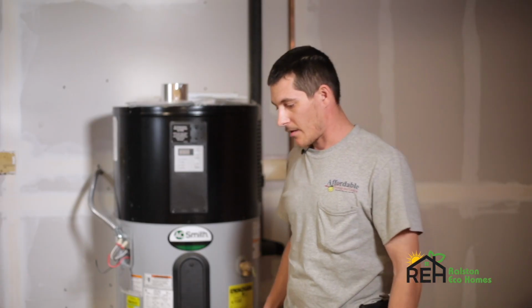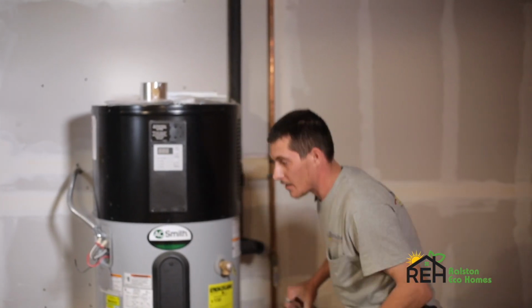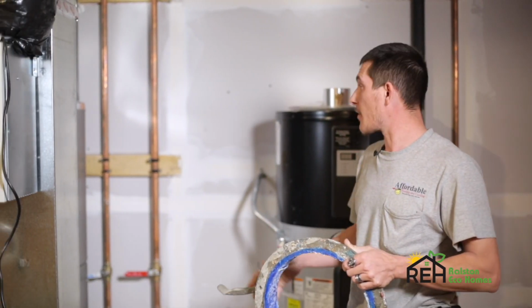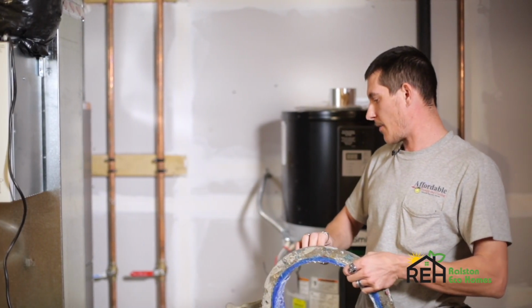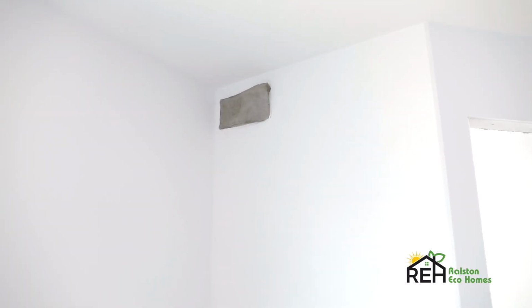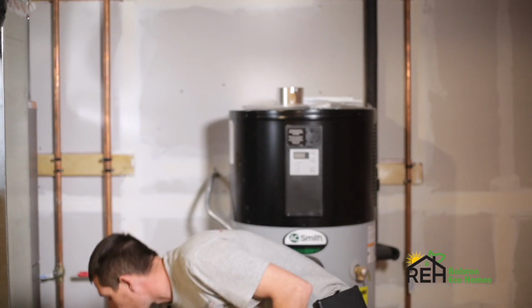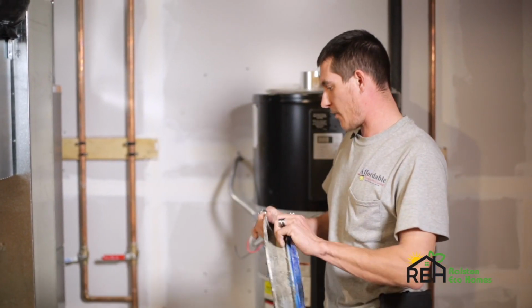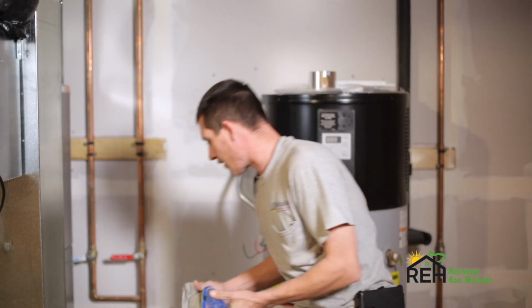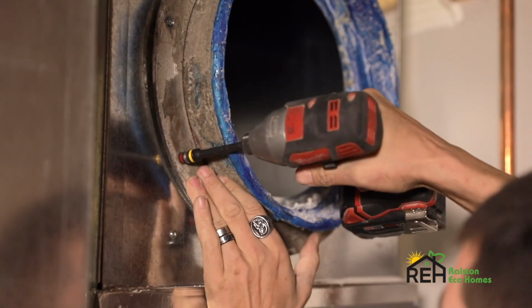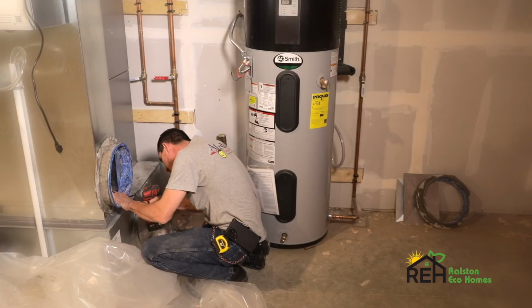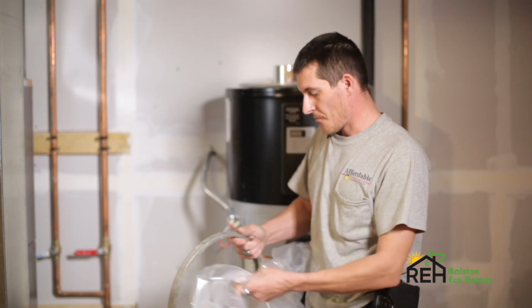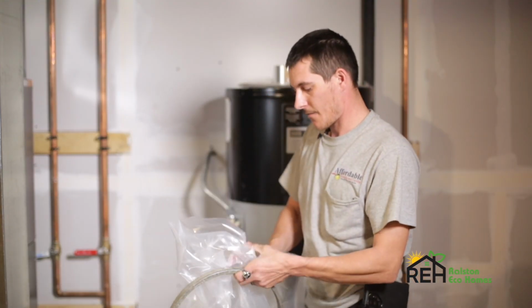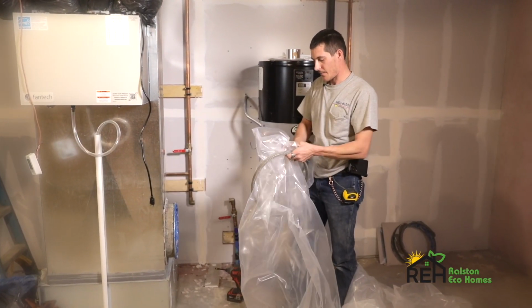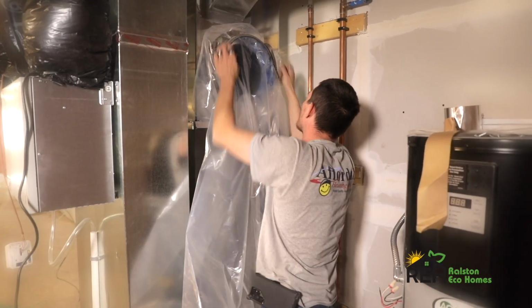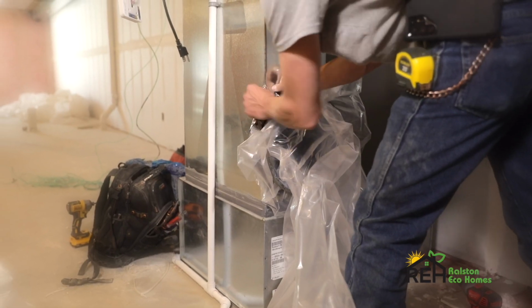All right, now let's hook up the bags. We've got these collars. They go into the furnace. Inside each part of the furnace, from the supply side and the return side, we've already got plugs put in place to protect the coil and protect the furnace box where the filter goes, so that no glue gets down in there. So we'll put these collars on. And then each bag will go on to the collars. And the bags are what the glue travels through to get up into the system to give it its seal.